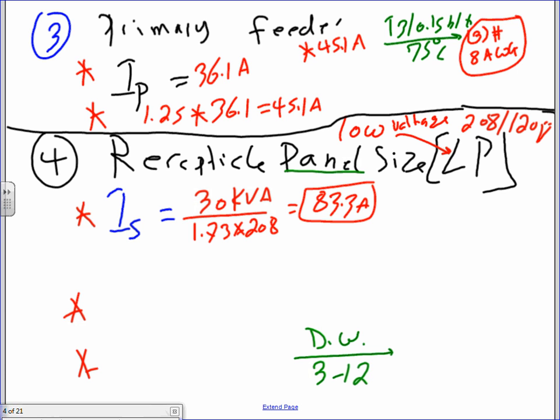And Derek is saying, well, Chad, we already got this information from the schedule, right? Okay. We are sizing, remember, the receptacle panel, LP, which is the low voltage panel, the 208/120. Then we're going to multiply by 1.25, assuming this will take care of the continuous load. I know receptacles are not continuous load and we derated them, but over the life of this panel, on the feeder, it's really nice to have 25% extra. It takes care of your voltage drop, and if you overload that panel a little bit. 1.25 times 83.3, and if you did this math, you're going to end up with 104.2 amps.